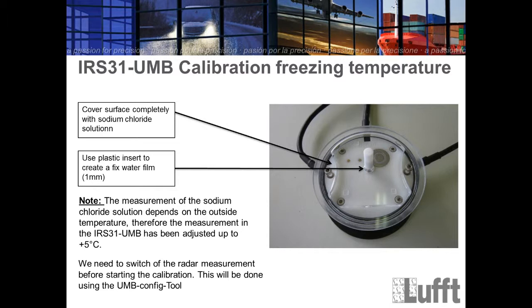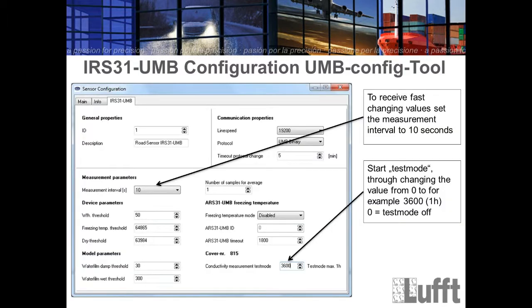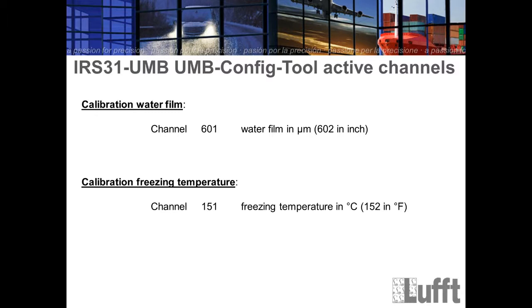Now I want to show you the channels which you have to activate for the different measurements. For example, for the water film calibration, the important channel in the channel list which you have to activate to check is channel 601. That's the water film in micrometers. Maybe you are using the sensor where the inch unit is used, so you can also activate 602, which is the inch unit for the water film. Normally this is used in the USA.